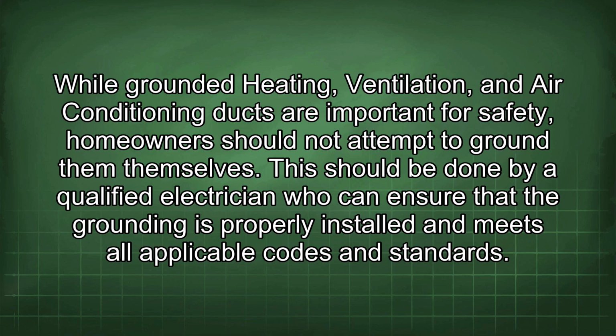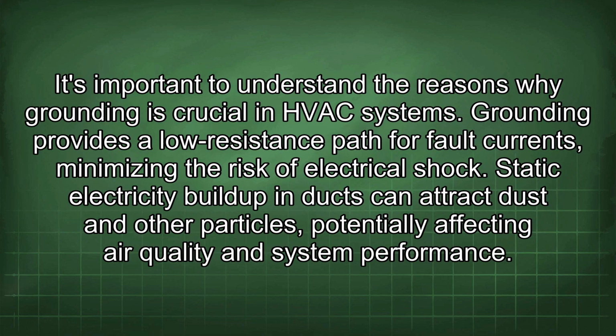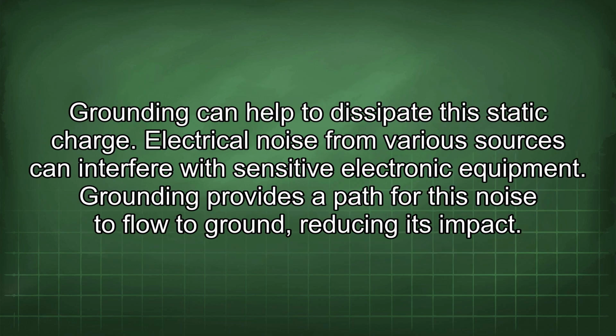It's important to understand the reasons why grounding is crucial in HVAC systems. Grounding provides a low resistance path for fault currents, minimizing the risk of electrical shock. Static electricity buildup in ducts can attract dust and other particles, potentially affecting air quality and system performance. Grounding can help to dissipate the static charge. Electrical noise from various sources can interfere with sensitive electronic equipment. Grounding provides a path for this noise to flow to ground, reducing its impact.